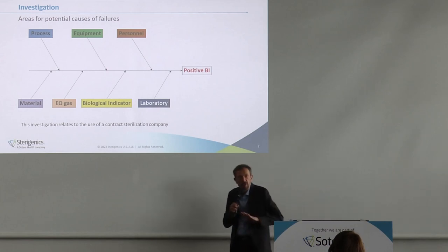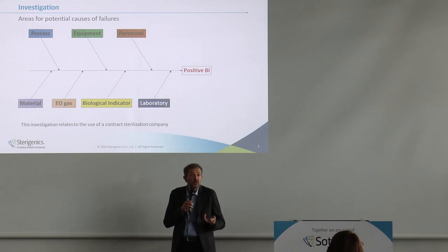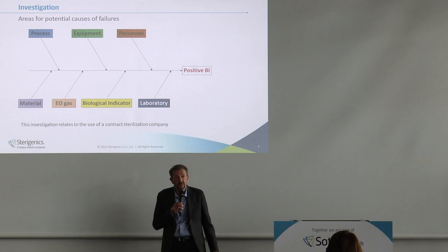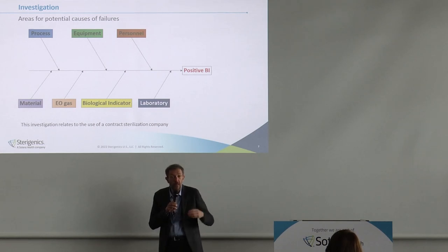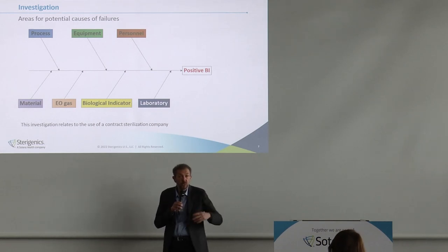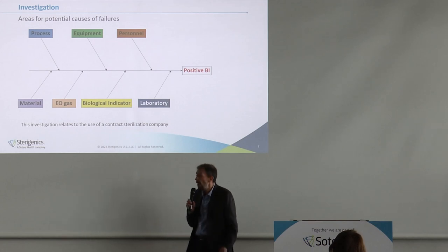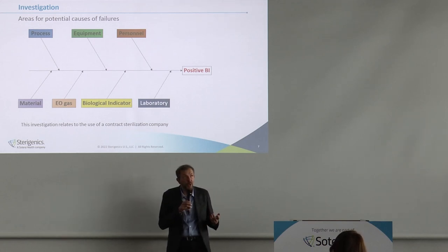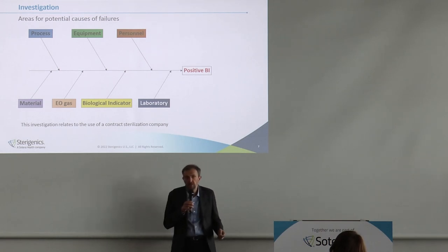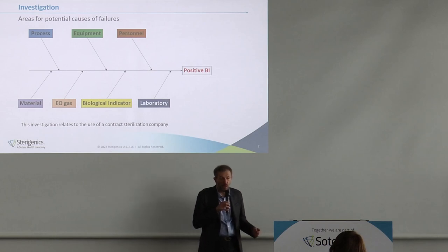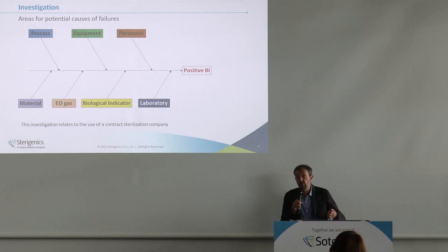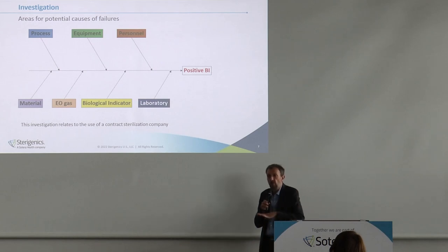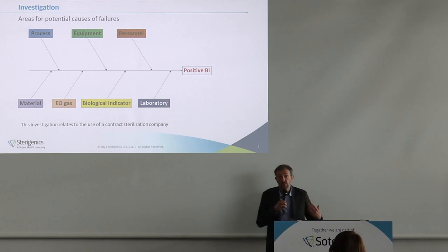It's easy to blame the BI because biological indicators are manufactured, so their quality, stability, and homogeneity can be questionable. You might find yourself at the end of a batch with a higher or lower population — fluctuations in BI quality can occur. They are also prone to desiccation: when exposed to extreme conditions they may become more resistant. And obviously the laboratory is the last piece to inspect — we need to ensure there is no source of external contamination and check the environmental quality and daily checks.